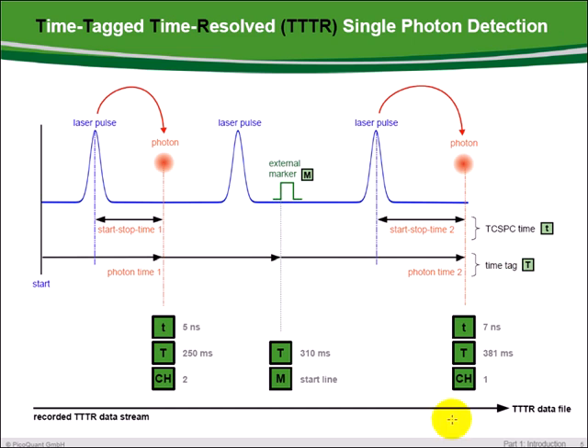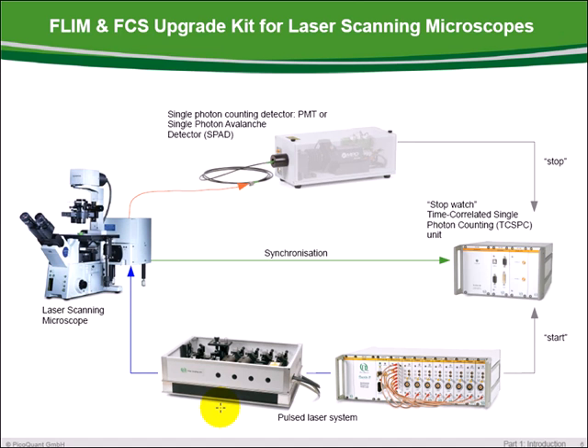This TTTR data format therefore collects the complete measurement information. In order to measure a FLIM image with a laser scanning microscope, pulsed lasers of different colors are combined in a laser combiner. The pulsed light is guided through a single-mode fiber to the microscope, where the fluorescence is excited in a sample. The fluorescence light is then delivered through a multimode fiber to a very sensitive single-photon detector, which creates a stop signal for the timing unit.